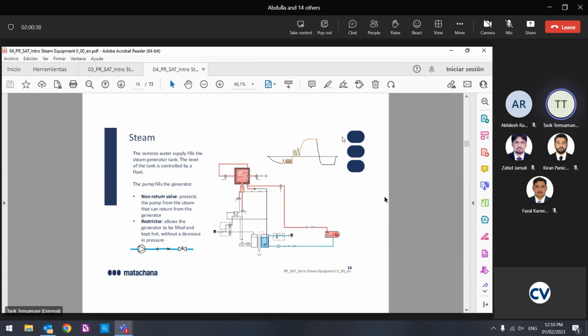In this case, we have to reach 3 bar. That means 2 bar additional. So once we reach this pressure, we start sending steam to the temperature circuit. What is the temperature? 135. In this, we don't care about the temperature in the steam generator. Temperature is in the chamber only. Temperature is not important in the generator. We control the pressure only. Only pressure.